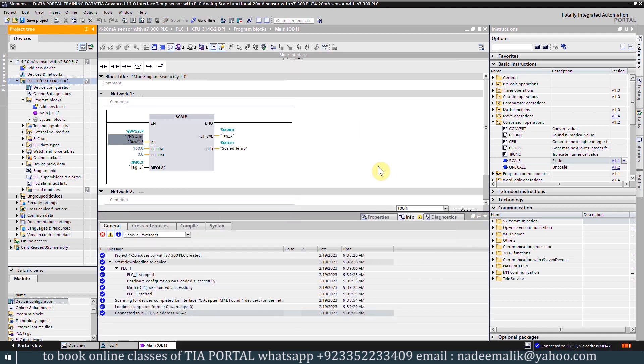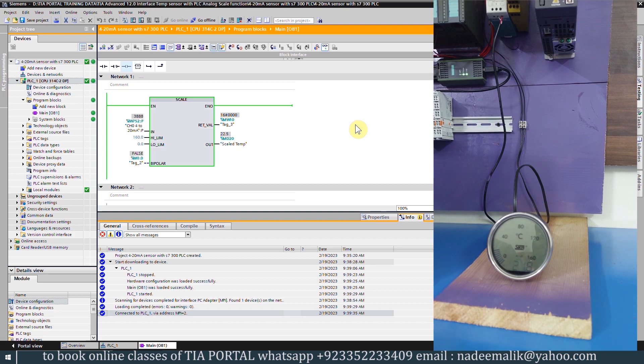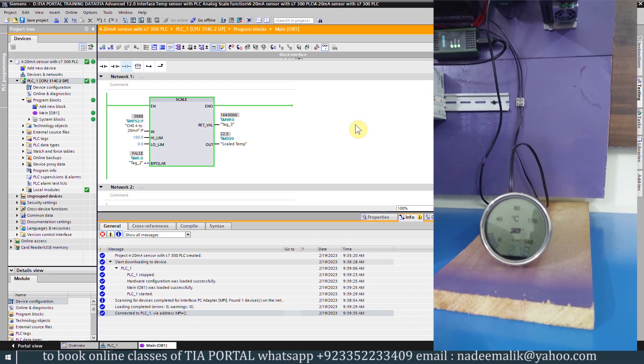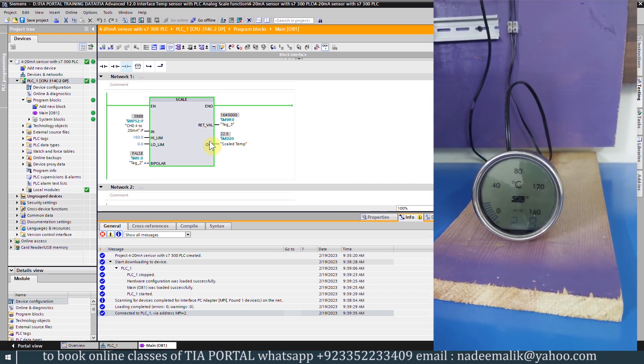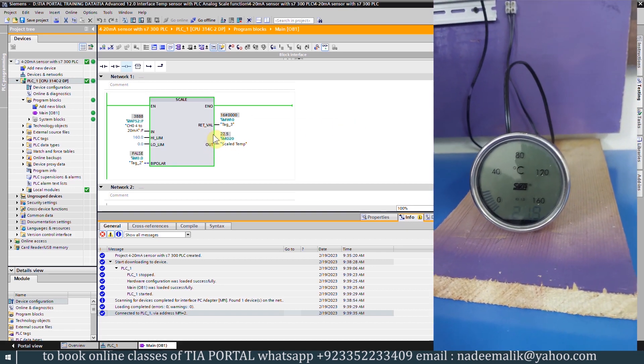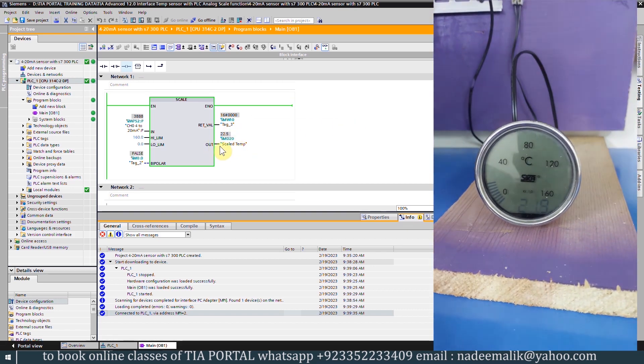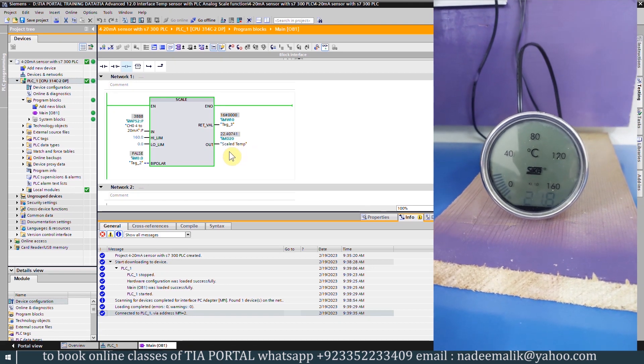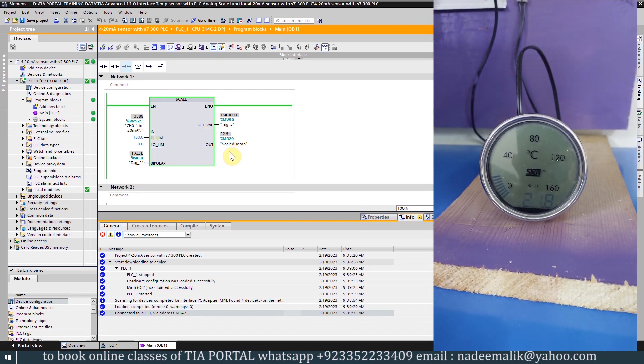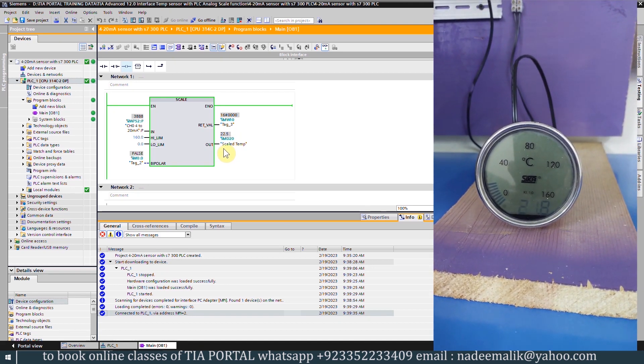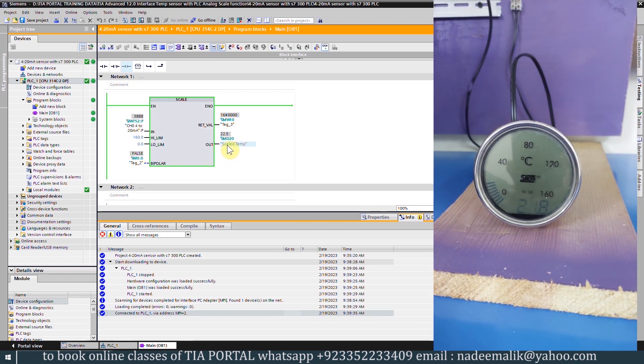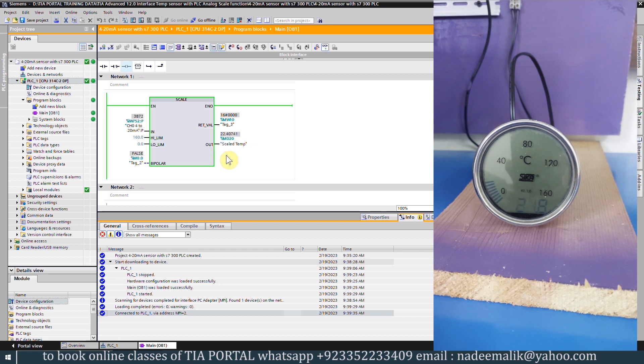As you can see, the scale function is working properly and scaling the analog 4 to 20 milliamp signal coming from the temperature transmitter between 0 to 160 degrees and showing the correct scaled value at the MD40 data register.